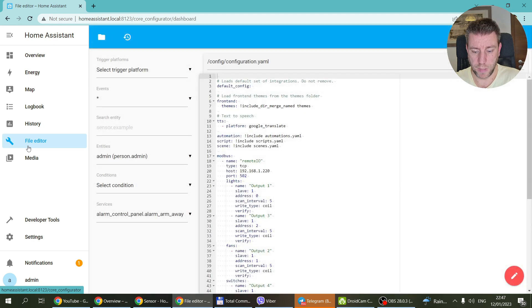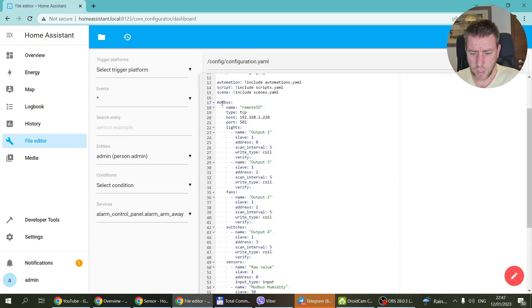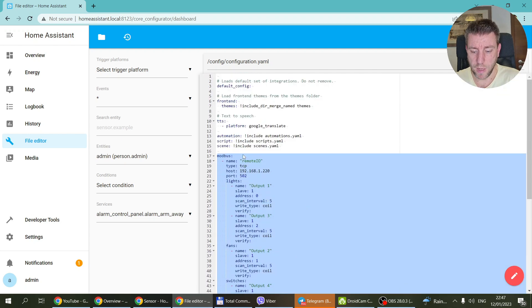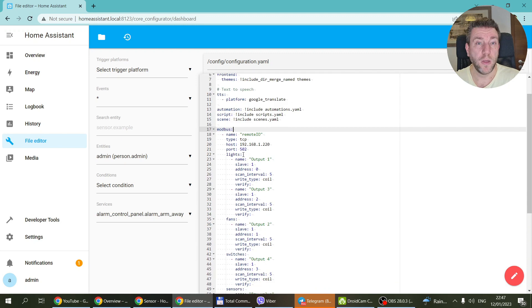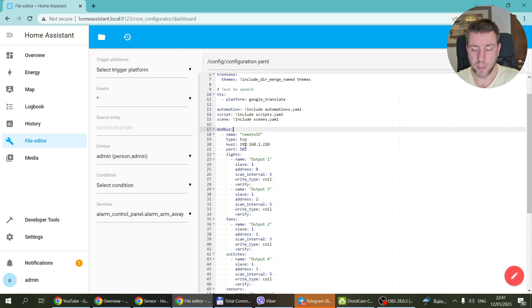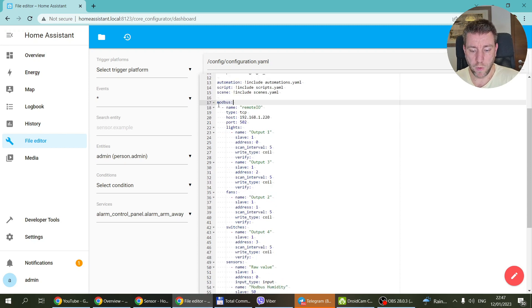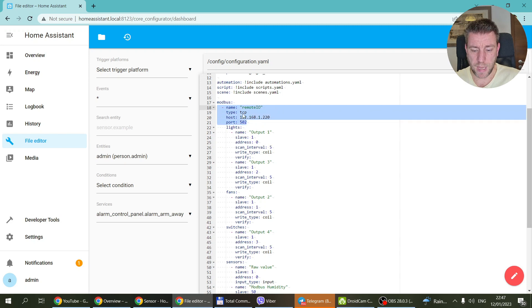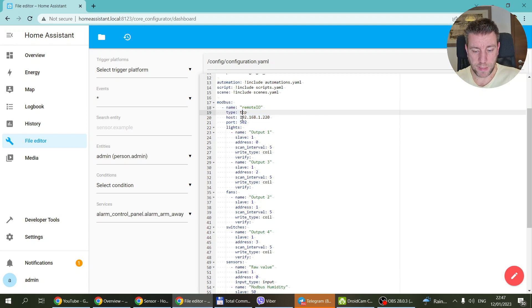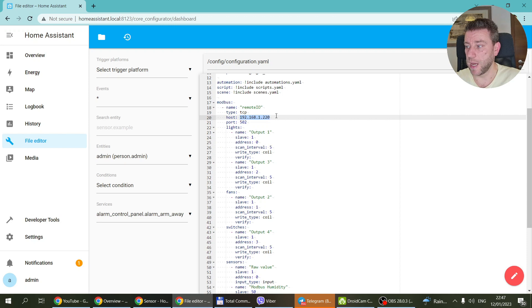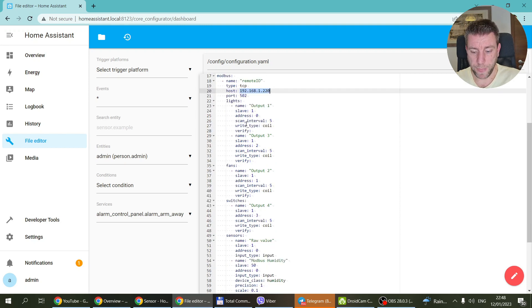And it is loading now. OK, so I have created all these settings for the things that you can see on the screen now. So let's start from the beginning. Oh, by the way, you're going to find a link in the video description where you can download this. At least not the whole YAML, but I think for this Modbus section which is relevant here. So first of all, I created a Modbus section because obviously we are going to read a Modbus device. And in the beginning I specified all the connection parameters. So the name of this device is remote IO and it is a TCP connection. This is the IP address of the device. That's the IP address of this remote IO gateway that I've configured in the previous video, and it's using 502 port, which is the standard Modbus port.